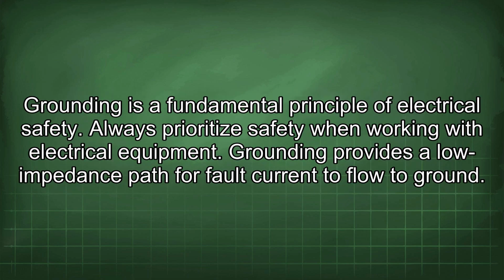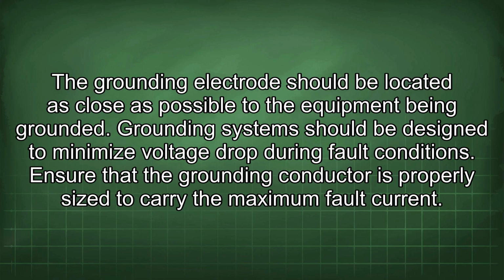Grounding is a fundamental principle of electrical safety. Always prioritize safety when working with electrical equipment. Grounding provides a low impedance path for fault current to flow to ground. The grounding electrode should be located as close as possible to the equipment being grounded. Grounding systems should be designed to minimize voltage drop during fault conditions. Ensure that the grounding conductor is properly sized to carry the maximum fault current.